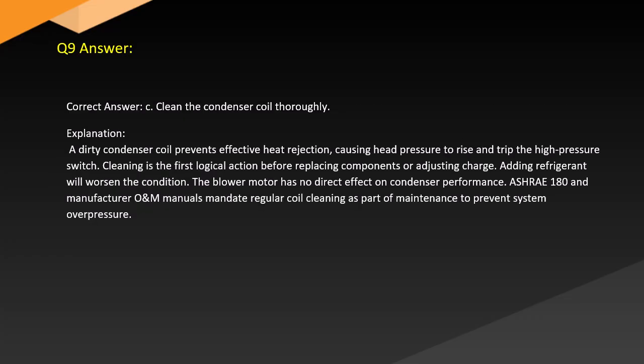Answer. Correct answer: C. Clean the condenser coil thoroughly. Explanation. A dirty condenser coil prevents effective heat rejection, causing head pressure to rise and trip the high-pressure switch. Cleaning is the first logical action before replacing components or adjusting charge. Adding refrigerant will worsen the condition. The blower motor has no direct effect on condenser performance. ASHRAE 180 and manufacturer manuals mandate regular coil cleaning as part of maintenance to prevent system overpressure.